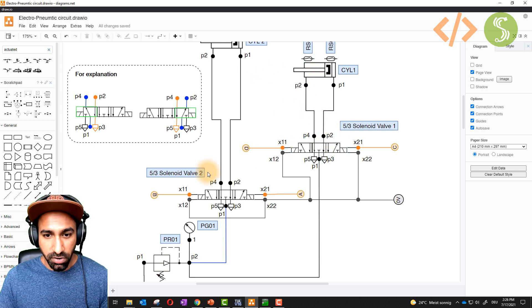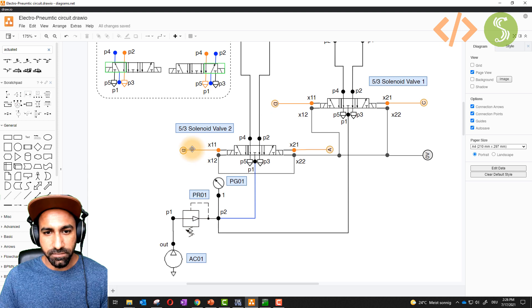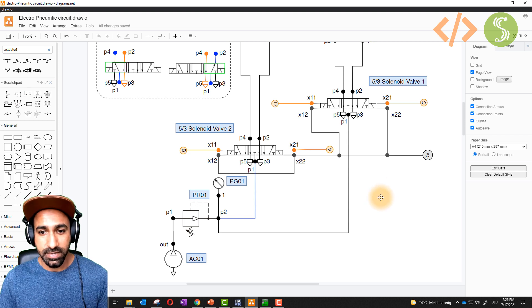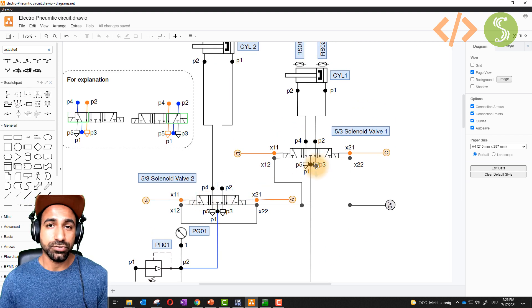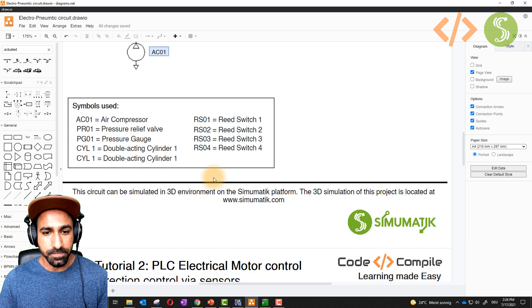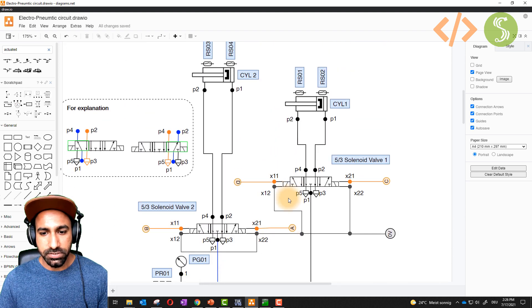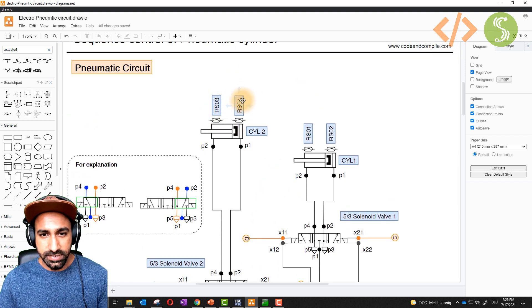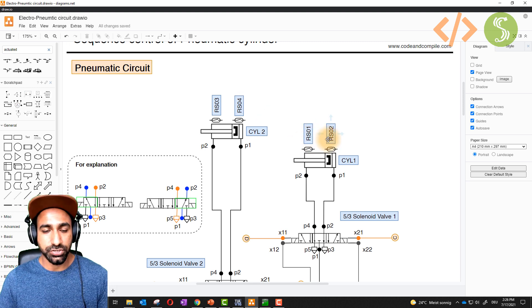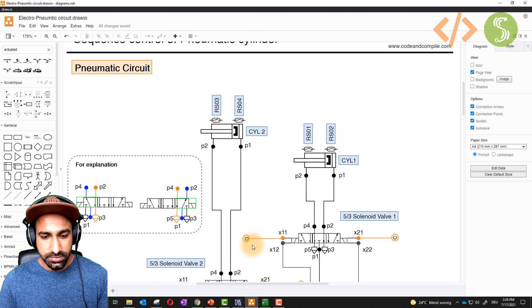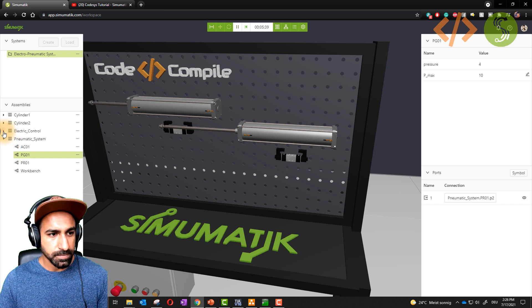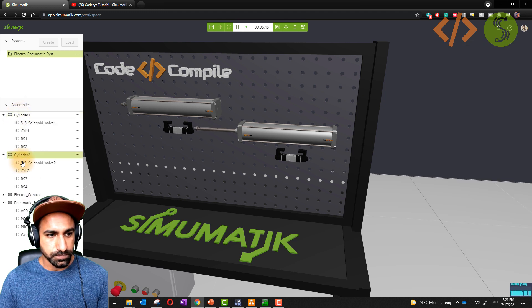Both cylinders are connected to these valves. A, B, C, D floating in the diagram are solenoids — the solenoids are connected to the PLC, so the on/off positions are controlled by the PLC. The solenoids are actuated by 24 volts. On top of the cylinder you will see RS01, RS02, RS03, RS04 — these are the reed switches giving feedback to the PLC. These reed switches are the orange devices you see here.